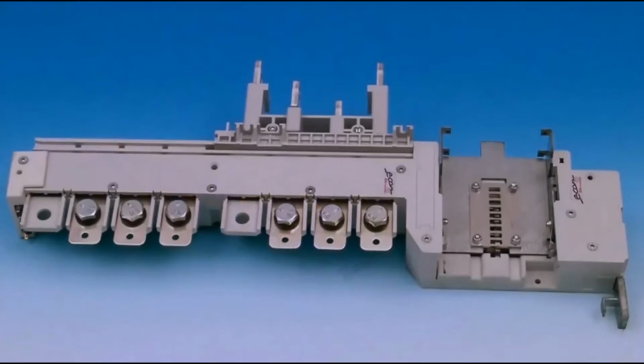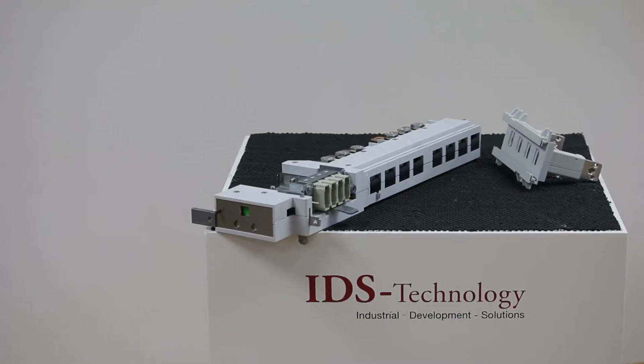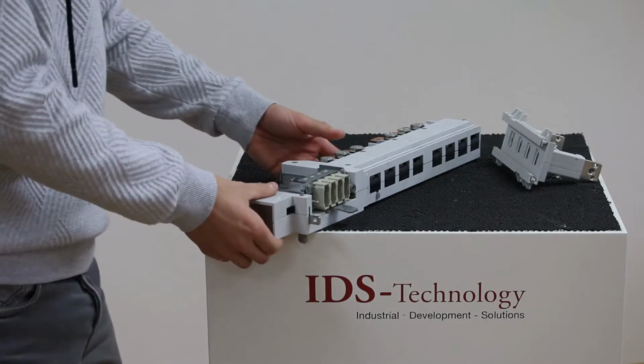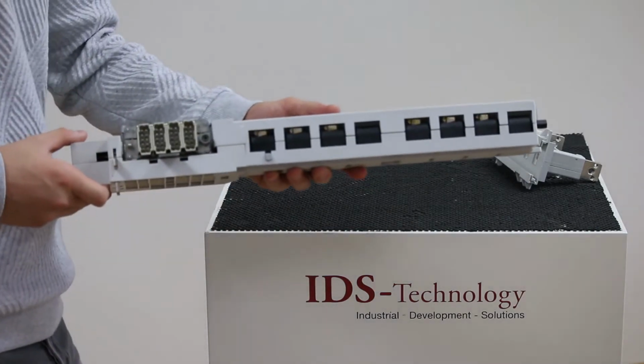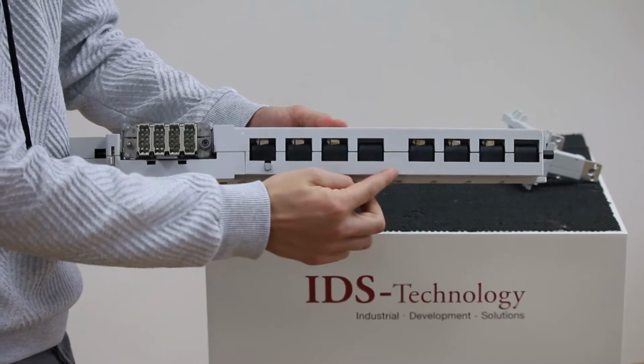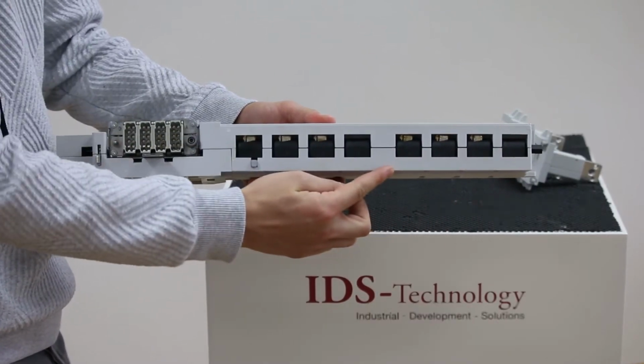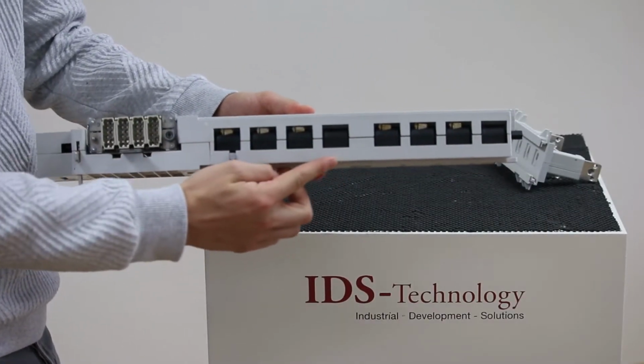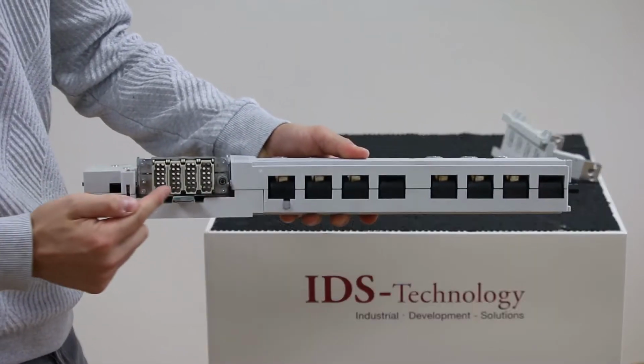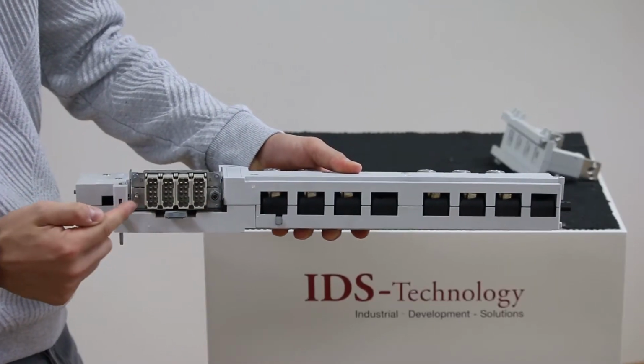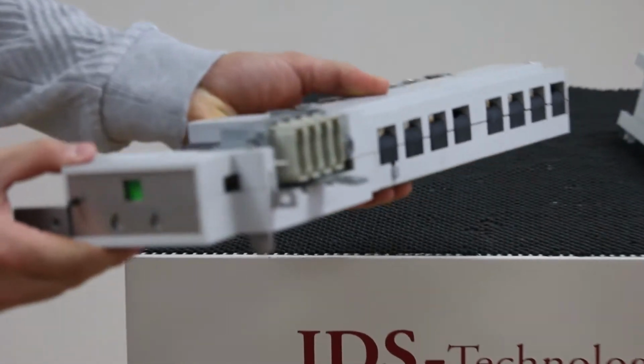The complete functionality of a conventional drawer is solved by the contacting module itself. This can be demonstrated with the contacting module and cable module without any additional mechanics around. The contacting module carries the contacting bolts for power in up to 4 poles and the same for power out. It has a mechanical slide to install the control plugs up to 48 pins from each kind of brand.